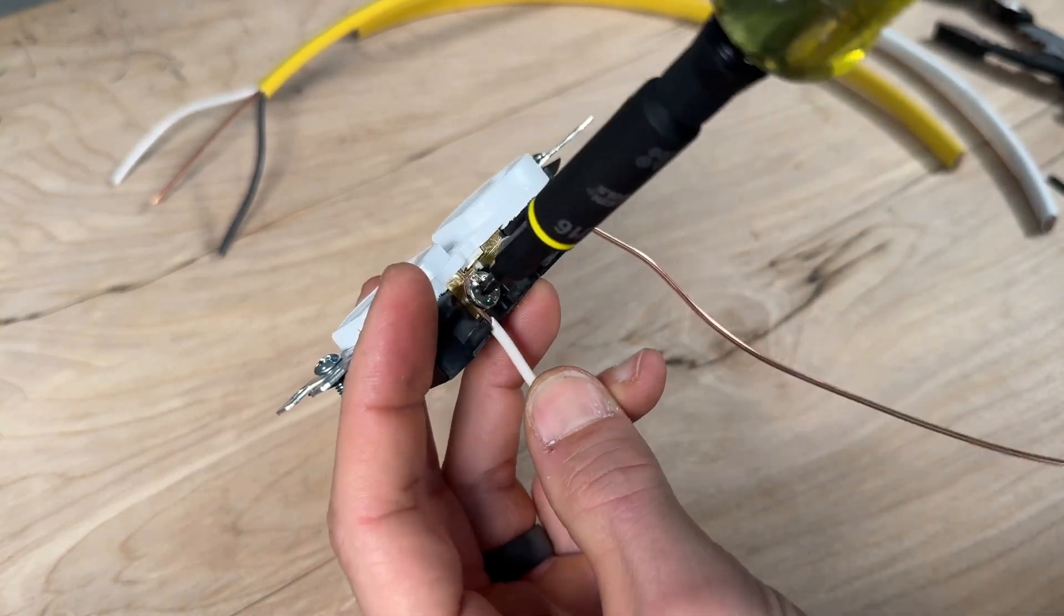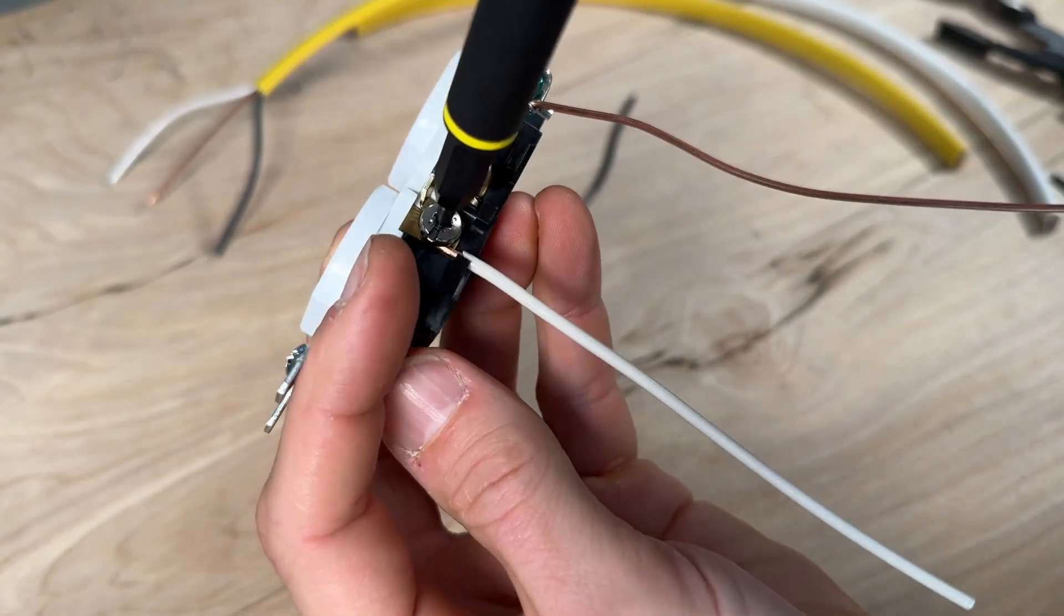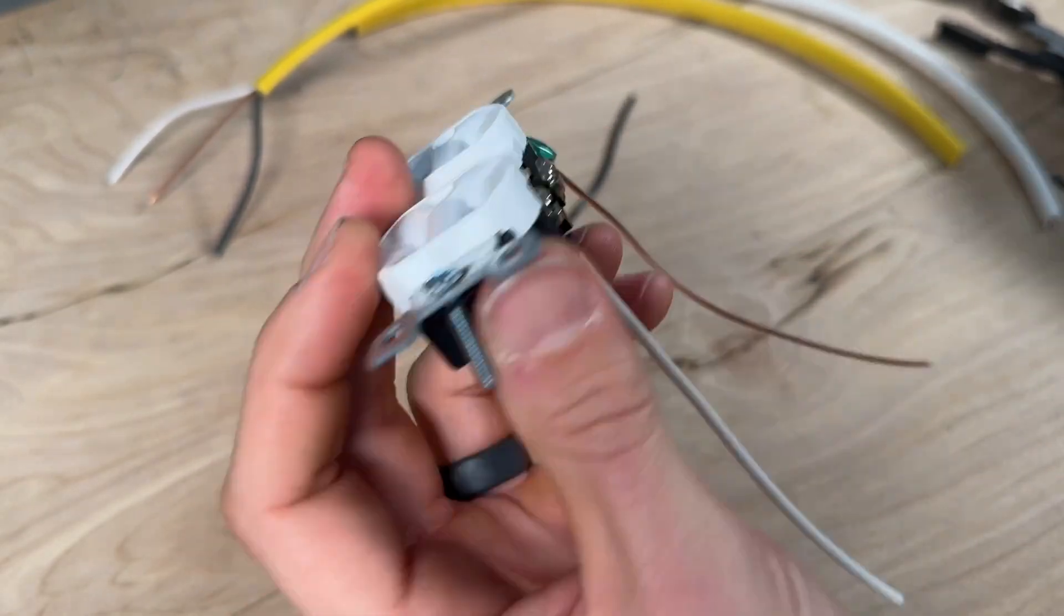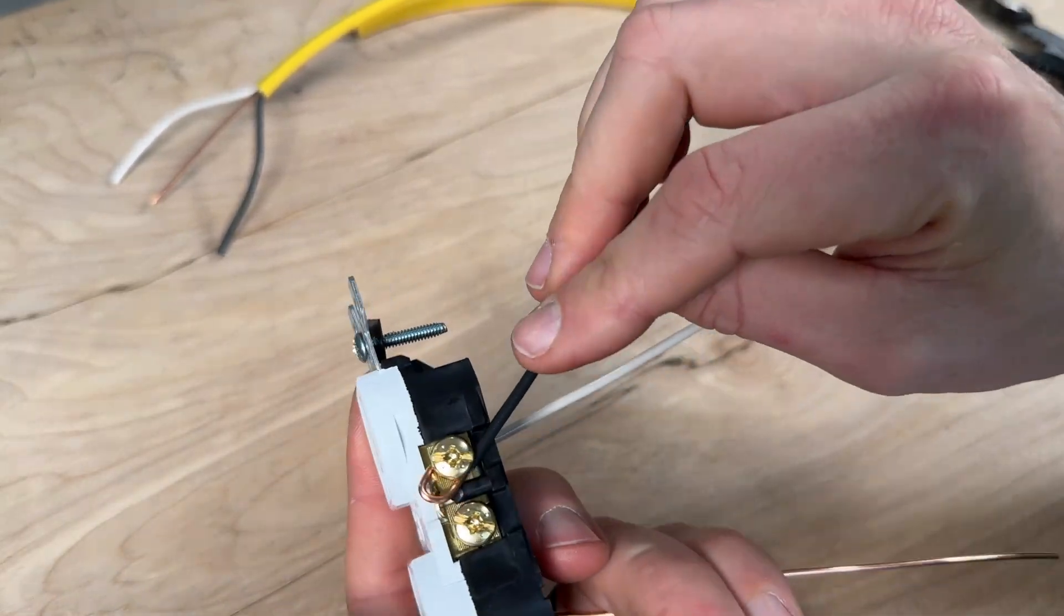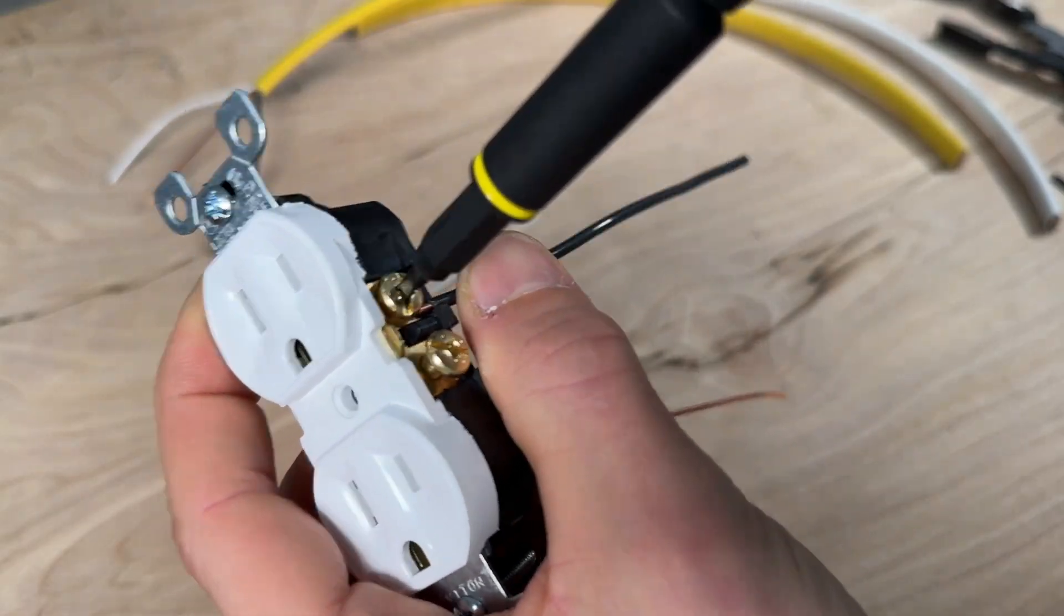We'll do the same thing here for our neutral on our silver screw terminal, again keeping it down and making sure it pulls tight to the screw terminal. Then you'll finish off with your hot side and the black conductor in the clockwise direction with your number one Robertson, tightening that down.